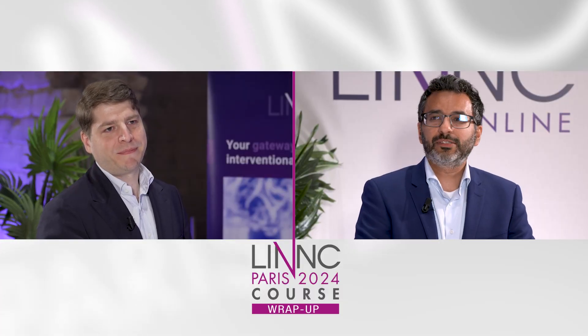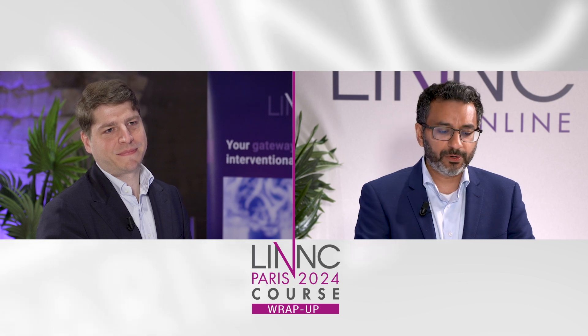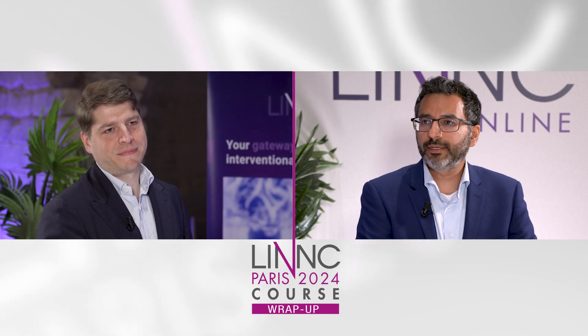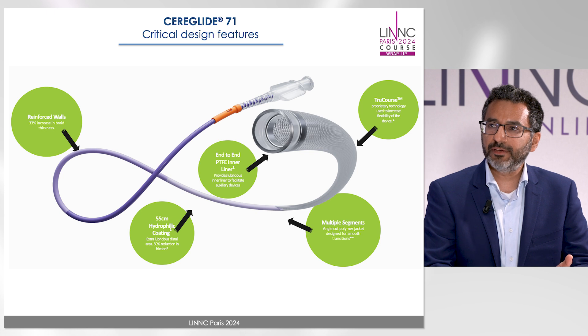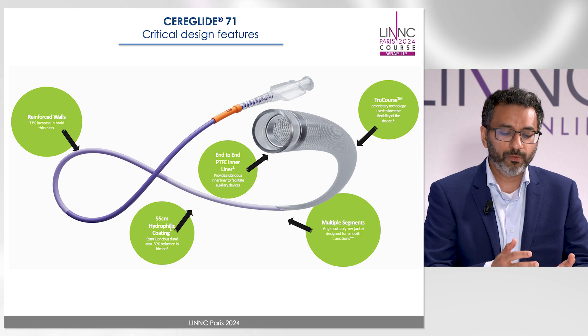And that's how we were able to design the CEREGLIDE 71. The CEREGLIDE 71 aspiration catheter is also an intermediate catheter with a 0.071 inch ID and 0.0825 inch OD, which is the smallest OD for this maximal ID of its kind. It has an end-to-end PTFE liner, 55 centimeters of hydrophilic coating, and all these features really help to make the catheter navigable with True Course technology in the manufacturing process.